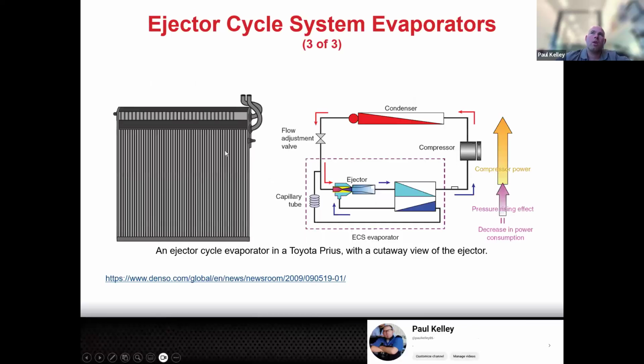So hold up, we've got like a doubled-up evaporator. The refrigerant goes into one, and then it uses the ejector cycle to kind of siphon it through, without making the compressor's job any harder. The ejector design pushes it through the secondary evaporator, providing extra cooling. To us, it doesn't really matter, you're just looking at this evaporator and it almost looks like a double, with a weird valve on it. Yeah, that's just the ejector cycle. Not a super big deal.